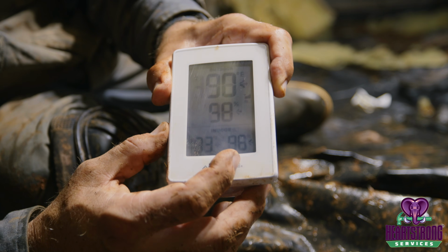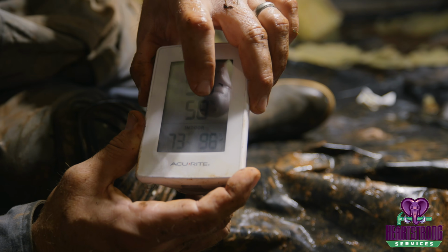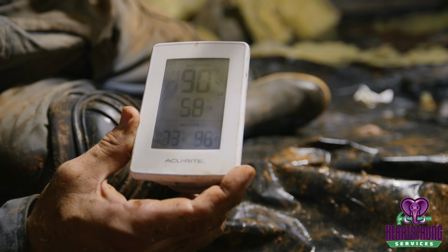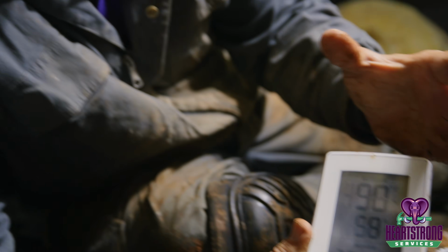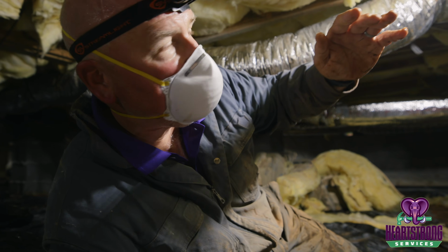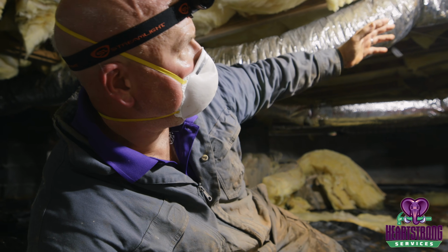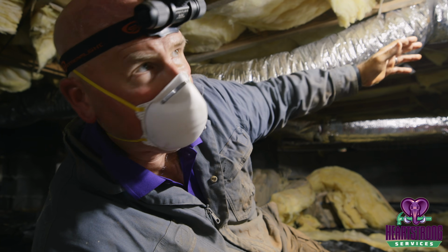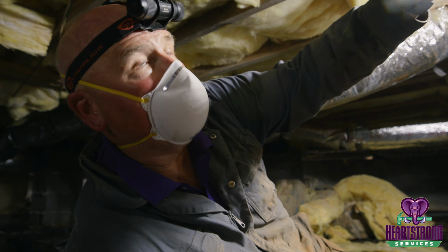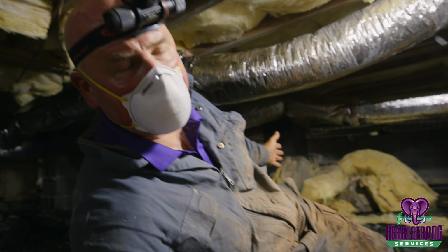This explains the science. Folks, understand that that hot air at 58% humidity comes inside this crawl space, and because the air is cooling, it has less capacity to carry moisture. Therefore, the relative humidity goes up dramatically inside this space. So much so that it not only causes the ductwork to sweat, the next thing that starts to happen is the insulation gets wet, which is why it's failing and falling all around me inside of this crawl space.